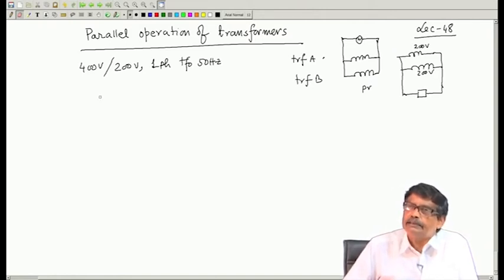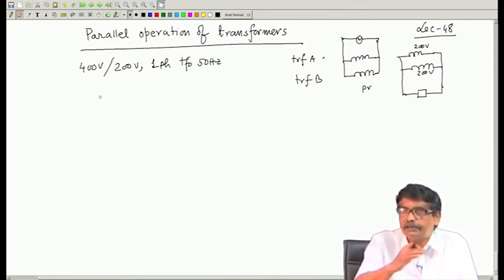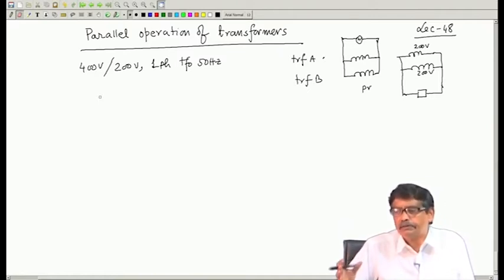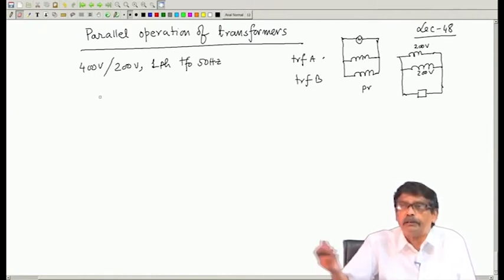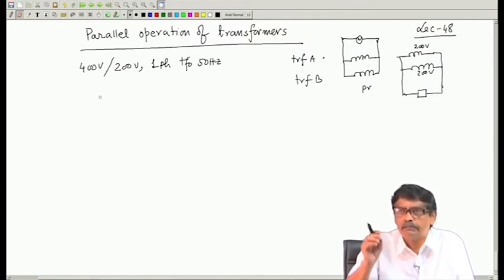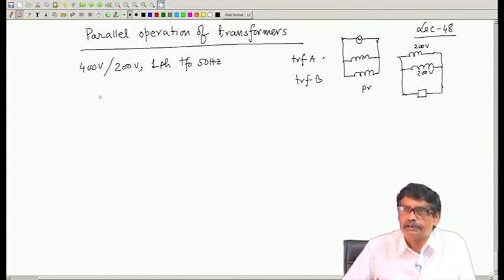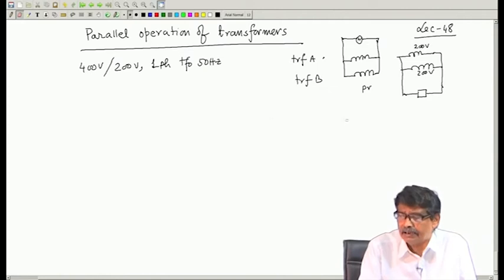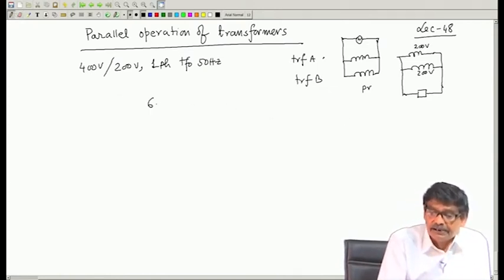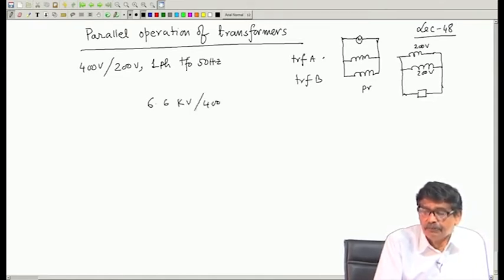at the last level there is a transformer whose rating is typically 6.6 kV to 440 volt, 3 phase, which we discussed earlier. Now, suppose a locality is to be supplied with 440 volt supply, where one supply line and neutral will go to every consumer, at 220 volt or 230 volt like that. But the problem is, suppose a locality is growing, and initially the demand of power is not that high. Suppose you select a 100 kVA transformer, to give you an idea, 6.6 kV to 440 volt, 3 phase transformer it is.